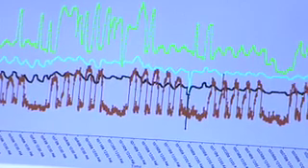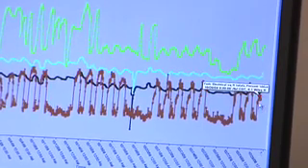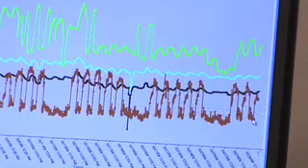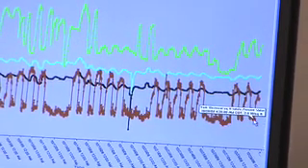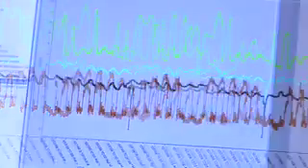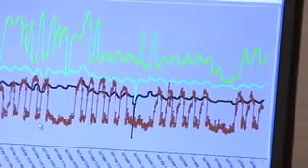That facility just today peaked at 4.1 watts a square foot, and its off-peak time is 2 watts a square foot. So you can see we have some base load here that we want to try to eliminate, and that will enable us to save some money.